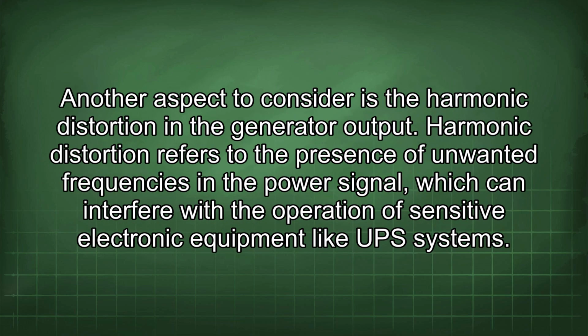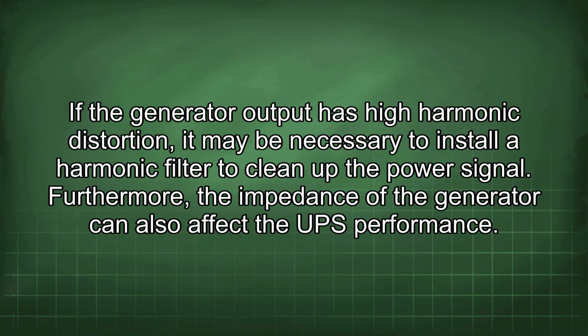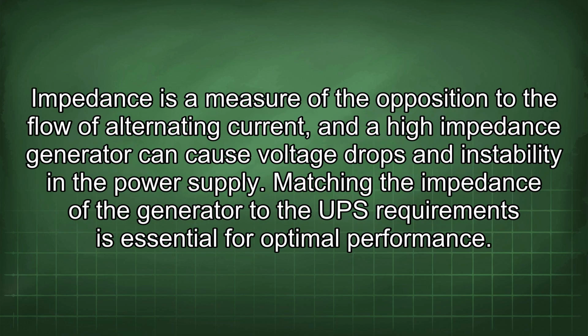Another aspect to consider is the harmonic distortion in the generator output. Harmonic distortion refers to the presence of unwanted frequencies in the power signal, which can interfere with the operation of sensitive electronic equipment like UPS systems. If the generator output has high harmonic distortion, it may be necessary to install a harmonic filter to clean up the power signal. Furthermore, the impedance of the generator can also affect the UPS performance. Impedance is a measure of the opposition to the flow of alternating current, and a high impedance generator can cause voltage drops and instability in the power supply.